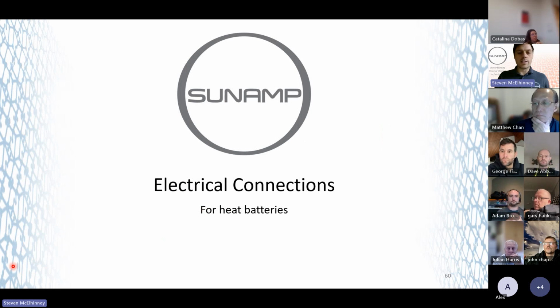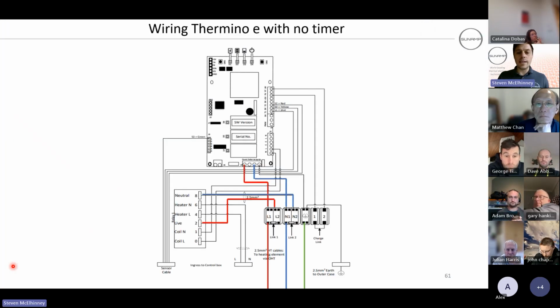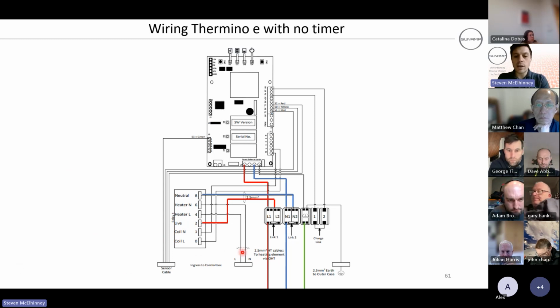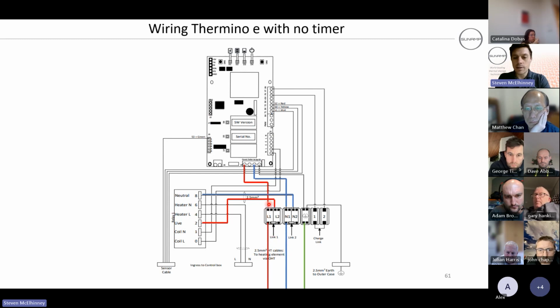So the electrical connections. Thermino E with no timer. So that's what you're going to see. So the unit itself, it's provided with a 3-core flex, 2.5mm 3-core flex. So you've got your permanent live coming in, neutral, and obviously earth. Permanent live comes in, powers the circuit board, but the link here links that permanent live across, and then hits our relay there. So we've got 2 permanent lives essentially coming in. And that's without a timer. So the charging link is in place here.